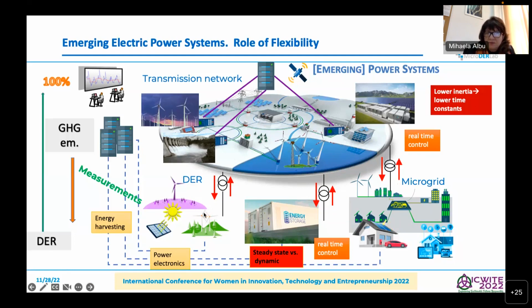So we ended up with this solution of generating small quantities of energy as close as possible to the consumption, at low and medium voltage, the distribution level, which might not be as dramatic as it appears now. But in order to use this energy, we needed power converters, static power converters, which means the available inertia in the grid is lower, because power converters have zero inertia, nothing rotating or moving, so the control needs lower time constants since the inertia is so low.